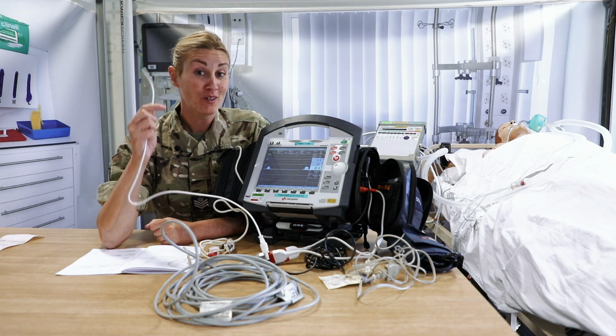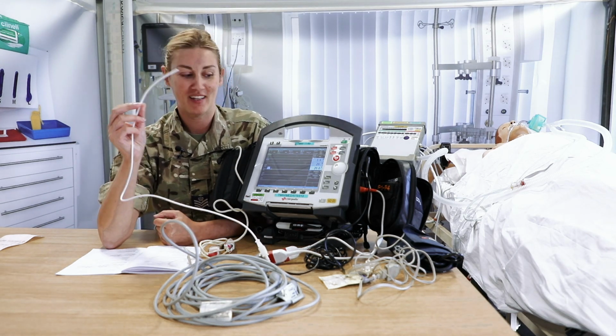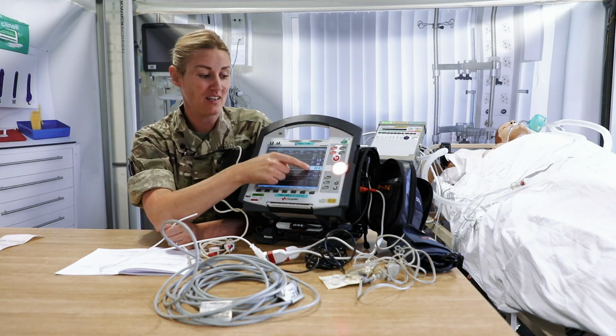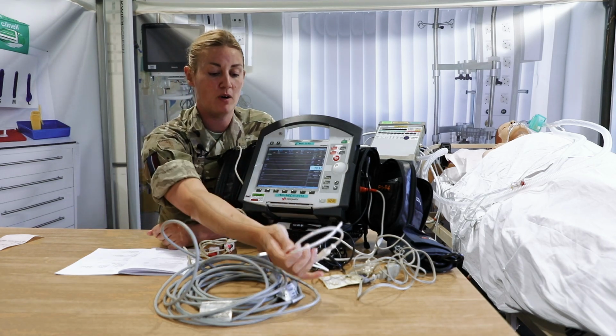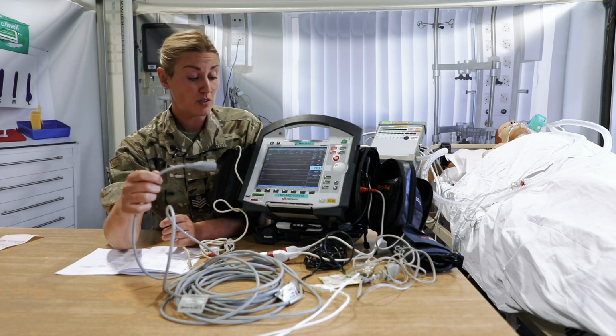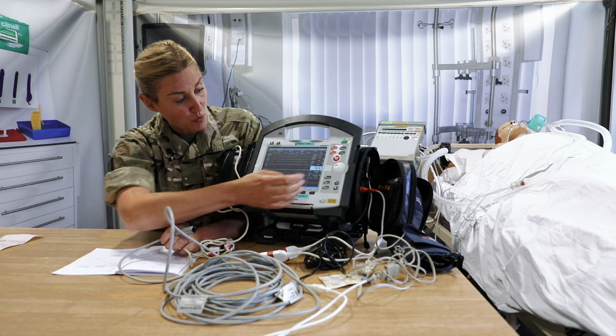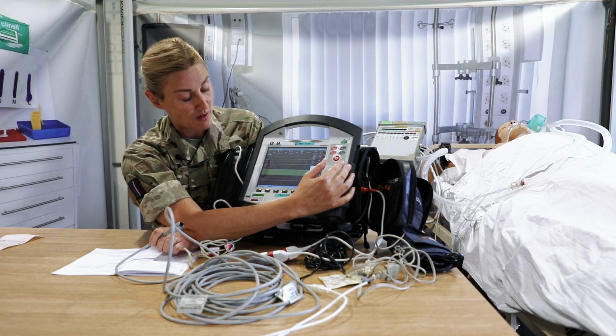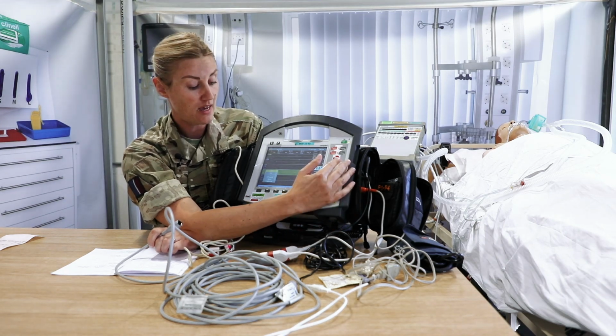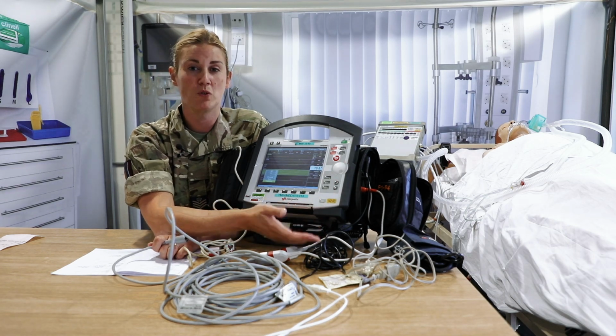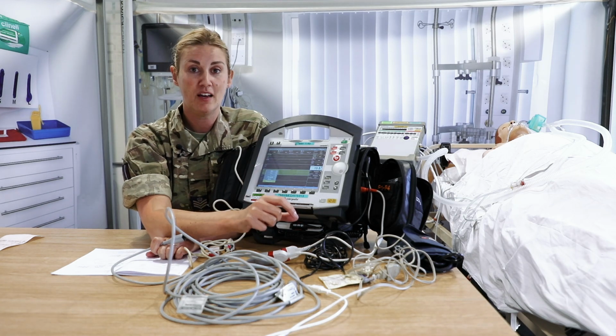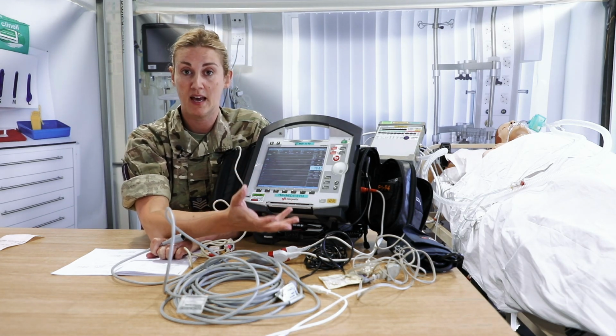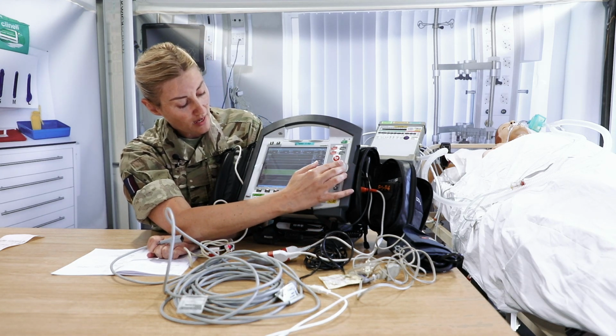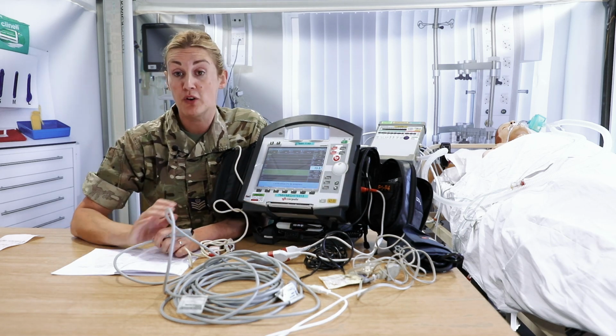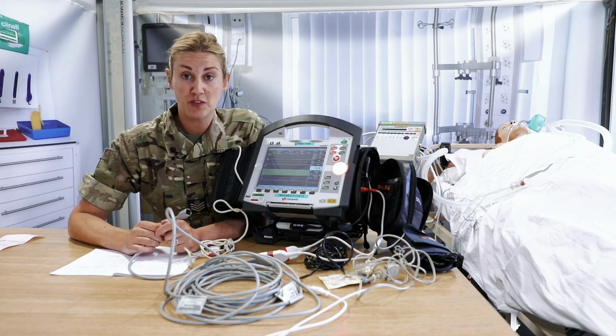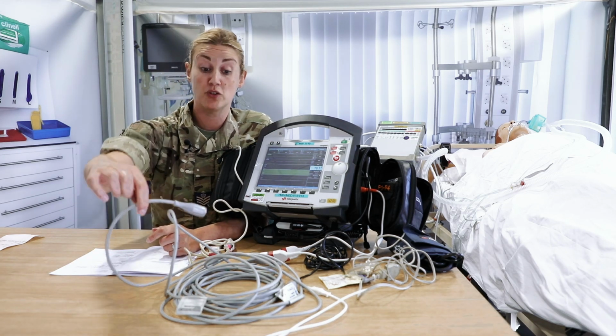The temperature probe, we wouldn't recommend actually sticking this up anyone or in anyone to check a temperature. You know it's working because it's reading the ambient temperature of about 20 degrees. So that's fine, that works. Plug in your dummy transducers to your invasive pressure leads. And what you're going to do is, using your jog wheel, you're going to scroll down to invasive pressure and click it. In there you have a calibrate function, and this is what Corpuls calls zeroing. So select calibrate at your transducer. Obviously open it to air in the same way as you would in real life, and then just click calibrate. This is not going to work because I haven't got it connected, but if it successfully zeros, it will say calibration successful. And you'll need to do that with all the leads that you're going to work with.